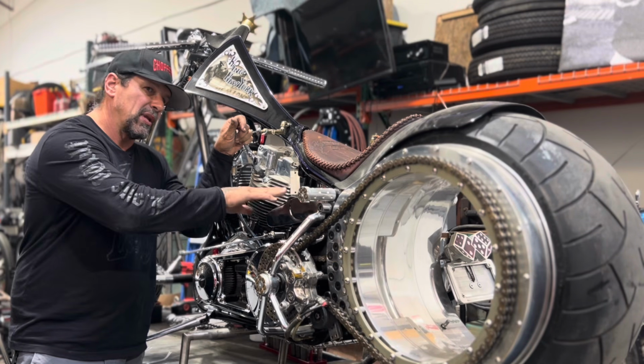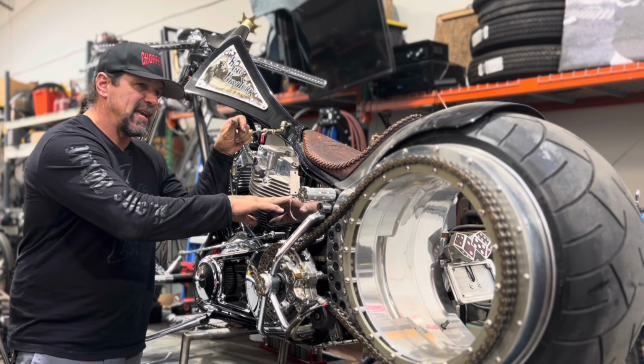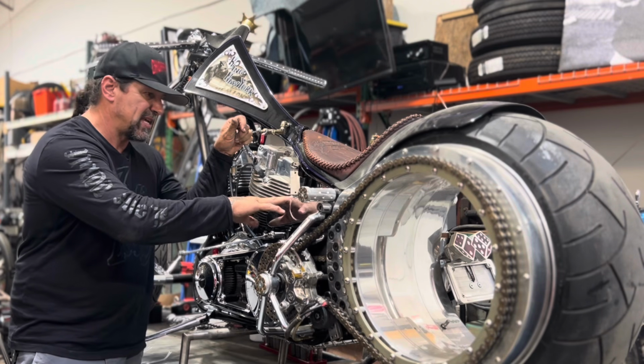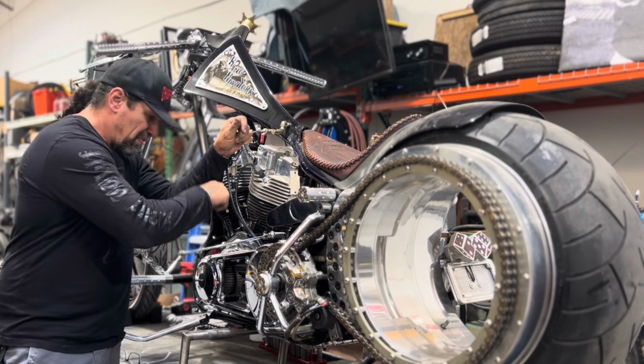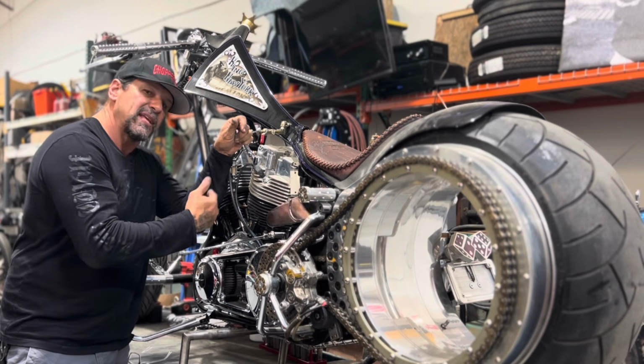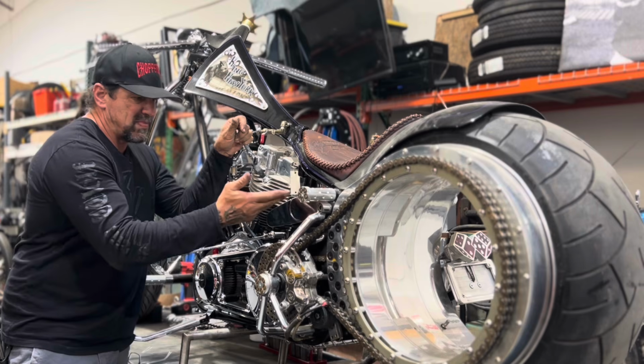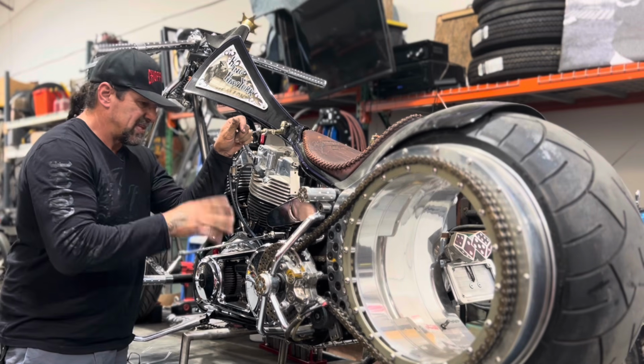So you want to make sure there's oil in the tank, but you don't want to fill the tank if it's been sitting for a long time, because when the tank is full and then the engine starts pumping the oil that's in the bottom end back to the tank, now your tank's over full and you need vent airspace inside the oil tank. So that's something to consider.